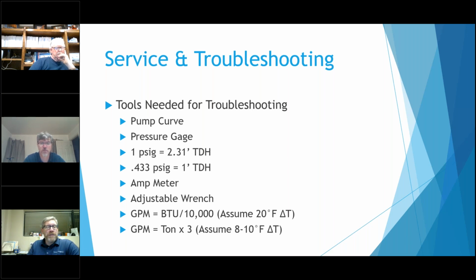And then to remember these two formulas: BTU divided by 10,000, assuming a 20-degree delta T, is GPM, and tons times 3 also gives you GPM if you've got a cooling system. Again, it's really just to get an idea of the flow that you might need out of the pump, because a lot of times we find pump tags are gone and we're trying to figure out what this pump is trying to do or what it should be doing.